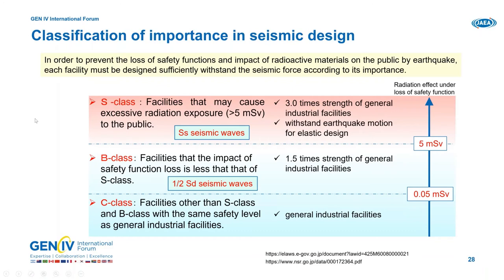Okay, this is the classification of seismic design. C class is a general industrial facility, and B class is one point five times stronger than the industrial facility. This means if the B class were broken, the radiation dose to surrounding people would be 0.05 millisievert. S class is three times stronger than a general industrial facility. For this importance, 5 millisievert is okay for the dose to the surrounding system.